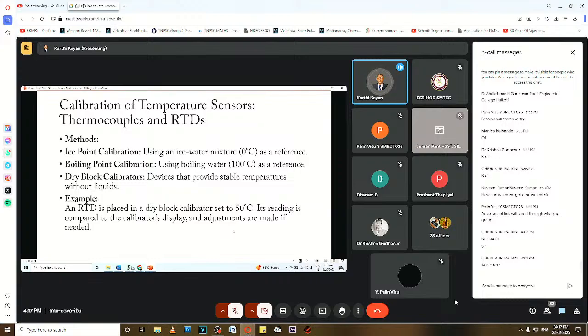Sometimes it shows 98 degrees Celsius, sometimes it shows 101 degrees Celsius. Otherwise, if it shows 102 degrees Celsius, it wouldn't be a good reading. So we have to measure everything in a perfect, calibrated way, and for that we have to use these calibrators. Next, for example, an RTD is placed in a dry block calibrator set to 50 degrees Celsius, its reading is compared to the calibrator's display, and adjustments are made if needed. These are some examples I am telling you.